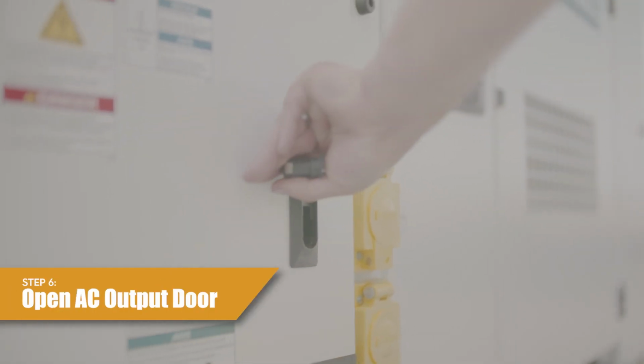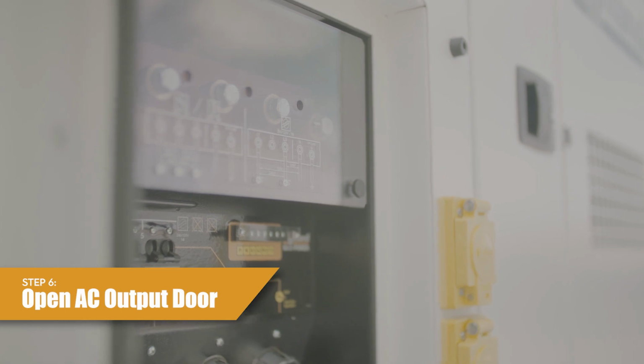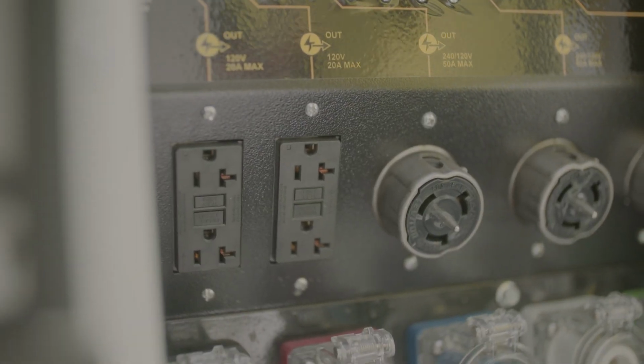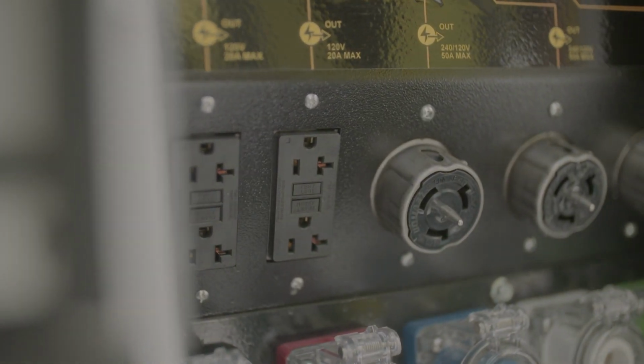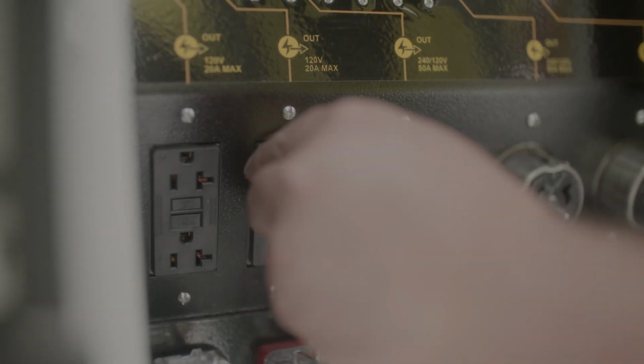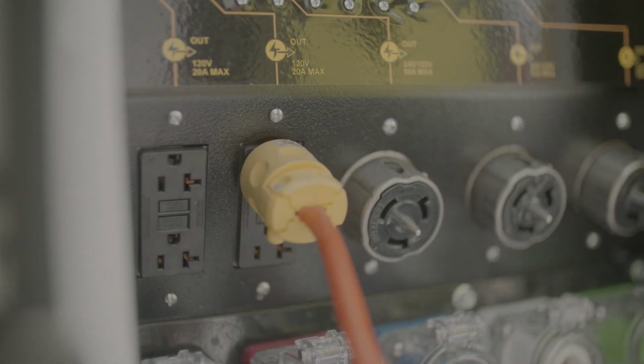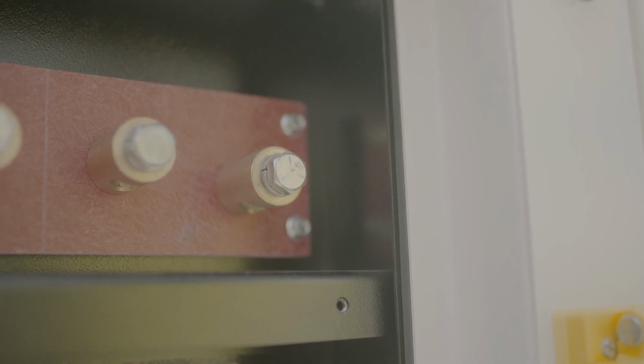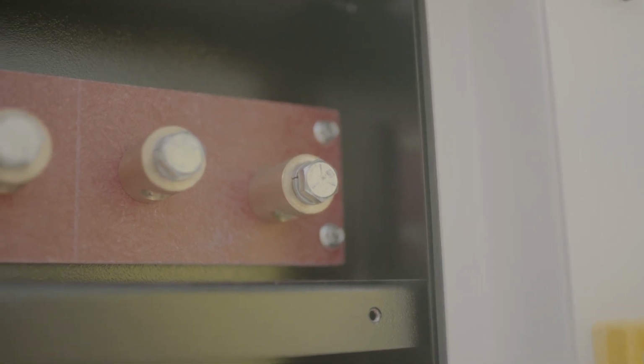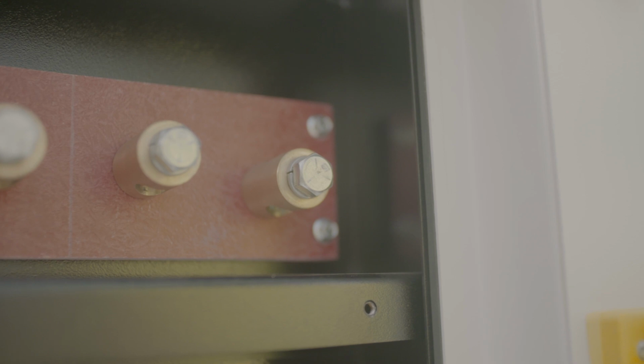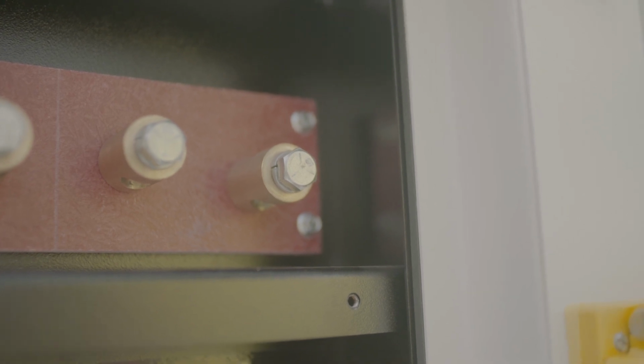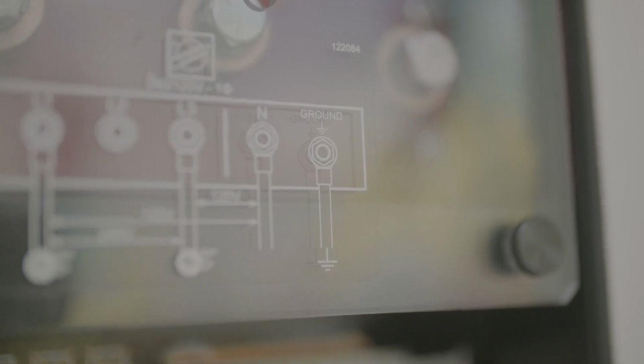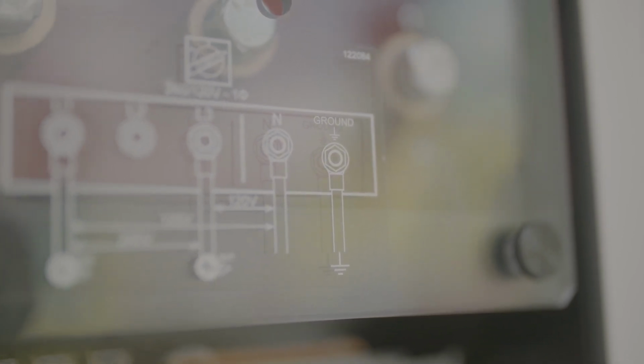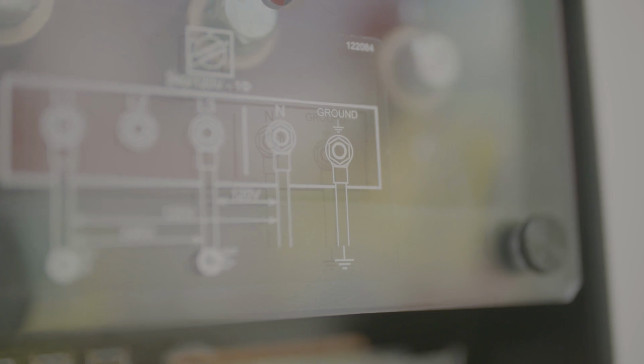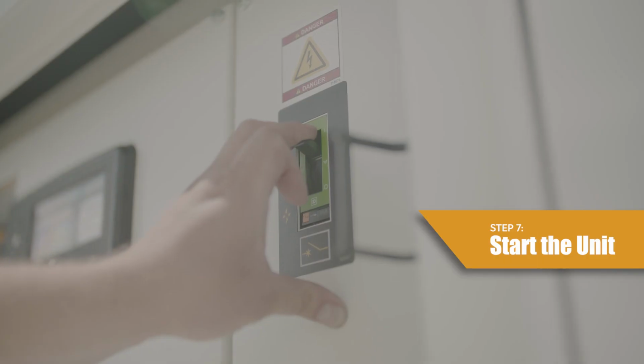Step 6. Open the AC output panel door. Connect cables or power cords to the connection lug plate or outlets. Refer to the operator's manual for cable loads and cable connections. Grounding the unit. Using a mallet, install a ground rod firmly into the ground, no less than 5 feet from the unit's grounding connection lug. Note: power cables and cords must be installed and connected to the AC outlet panel prior to operating the unit and starting the engine.